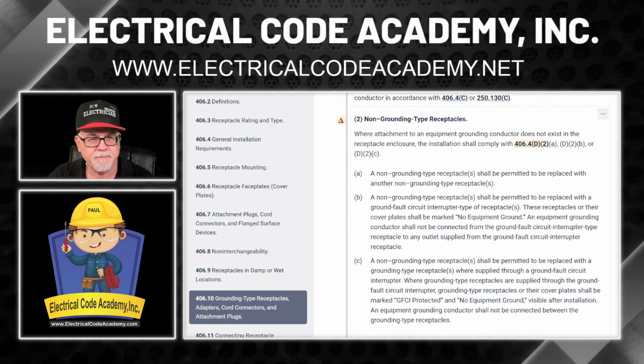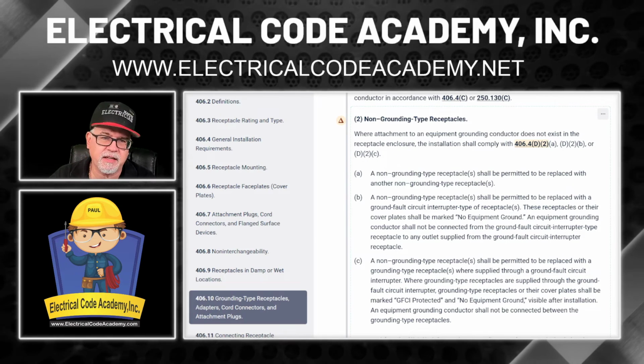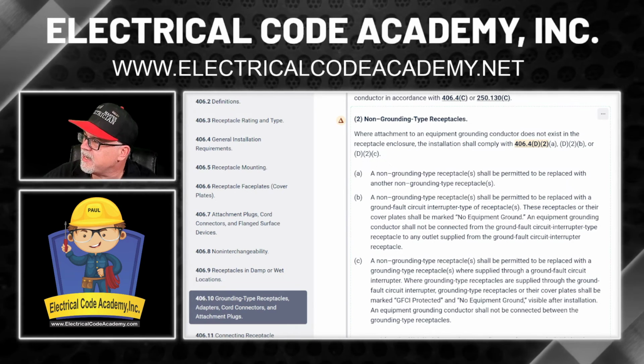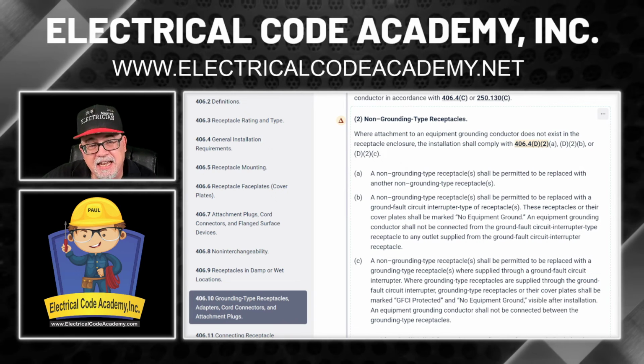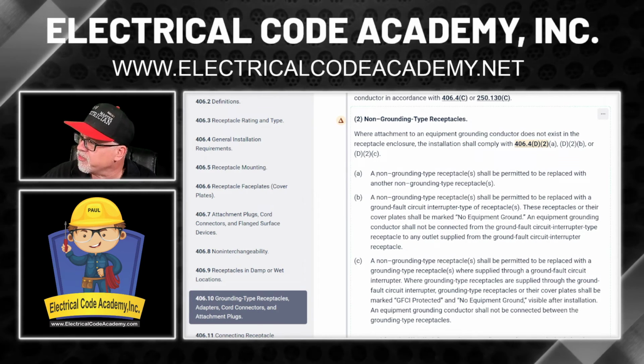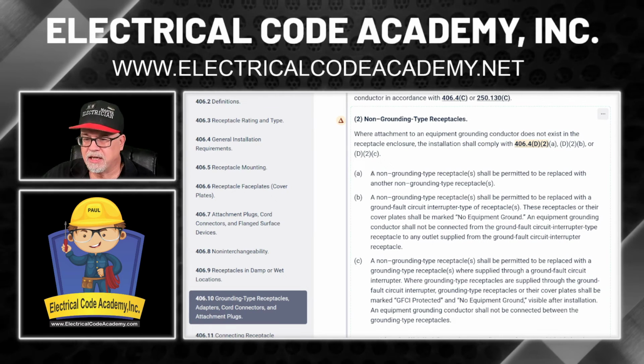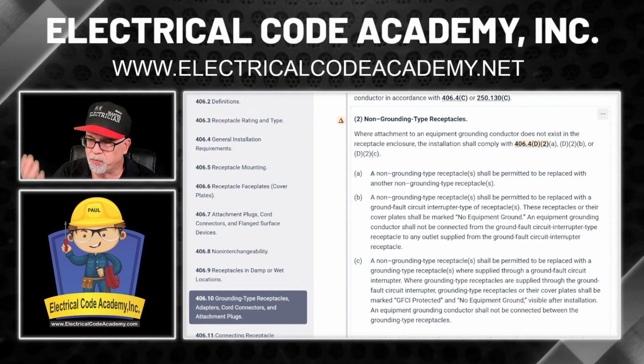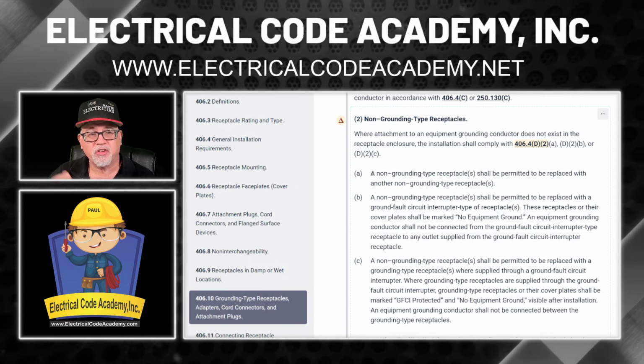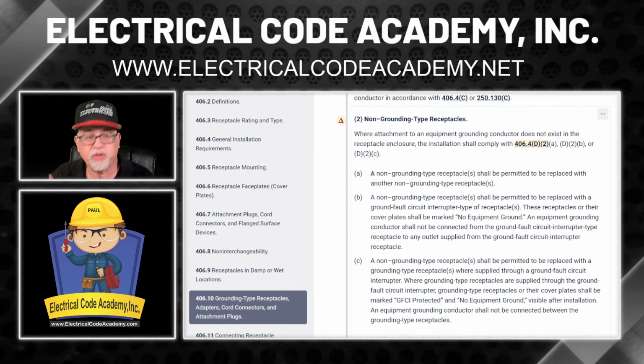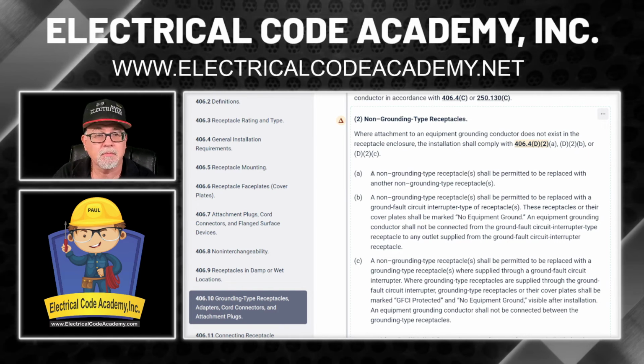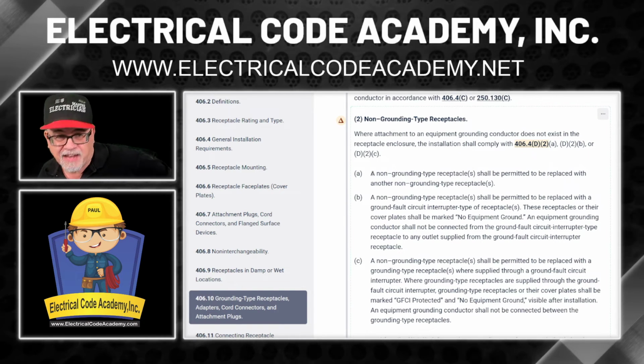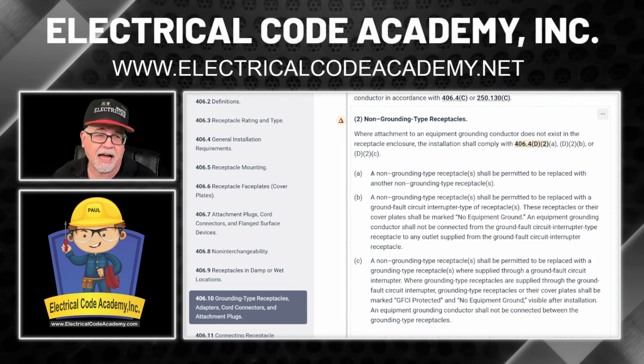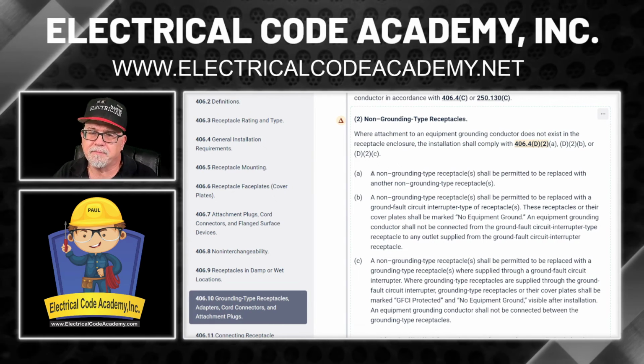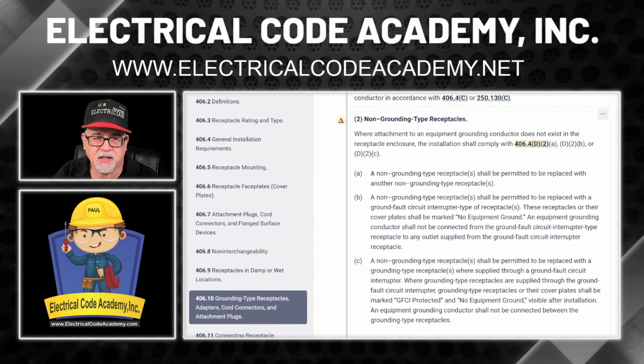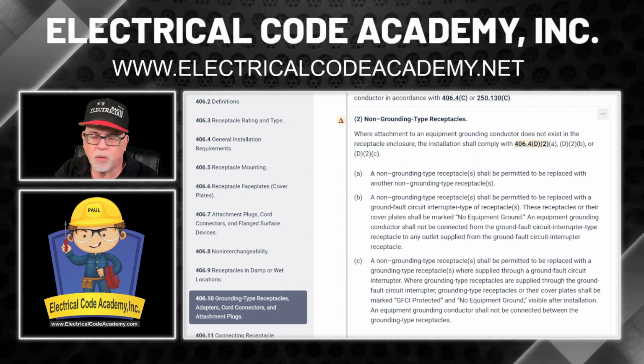So non-grounded type. You see that we have an A, B, and a C there. So we're at 406.4D, and there's a D2A, a D2B, and a D2C. Now, the first thing that you could have done, if you're a service electrician just going out to a job, and you have a damaged two-prong receptacle, is you could simply replace that two-prong with another two-prong, okay? A non-grounded type. The code allows for that. It was okay at the time it was originally installed, so I'm going to allow you to put it back the way it was. But people want the three prongs for convenience, plugging in things. They want it. But we don't have an equipment ground there.